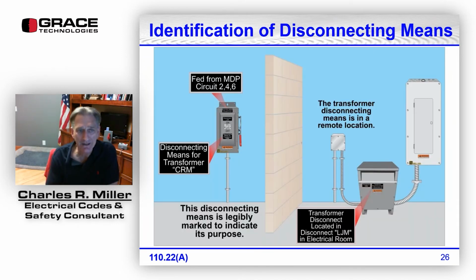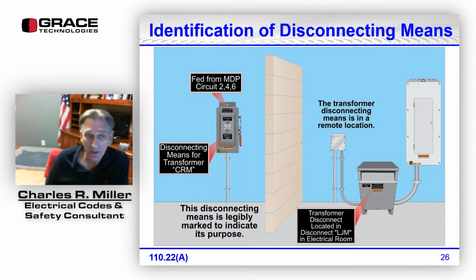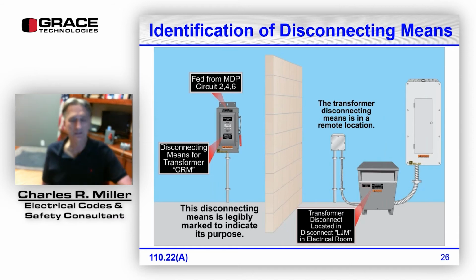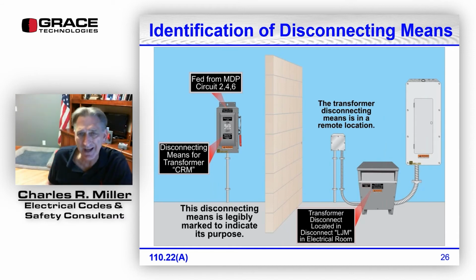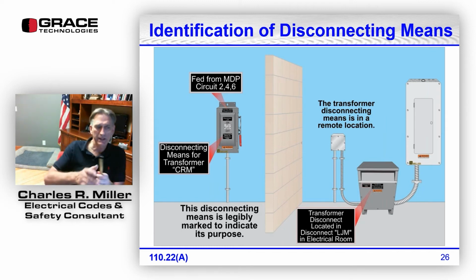So here's an example. This disconnecting means on the left is from the main distribution panel, circuit 246. It shows that it's a disconnecting means for transformer CRM, and the marking is legible. Now, on the transformer, we have to have, and this is out of another place in the National Electrical Code, if the disconnecting means is not within sight of the transformer, it has to have a label showing where the disconnect is.